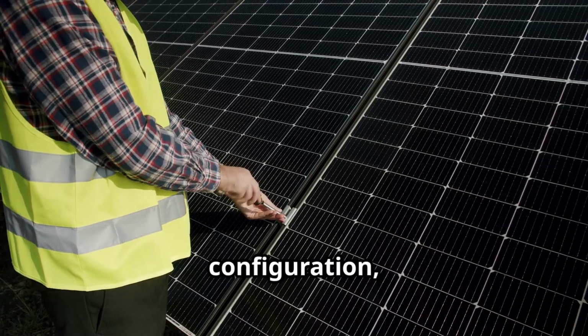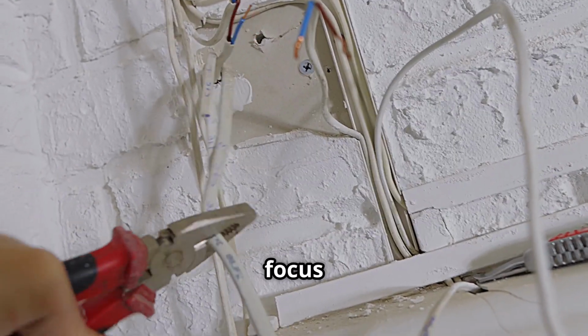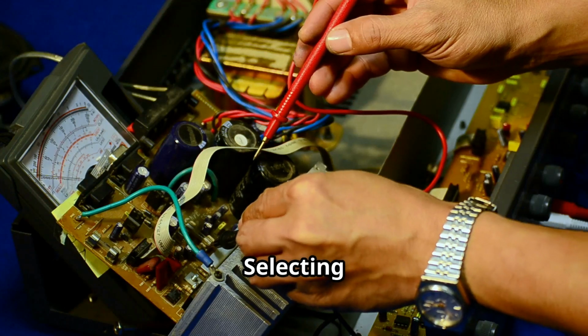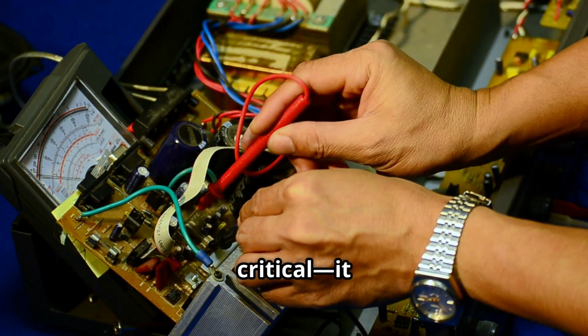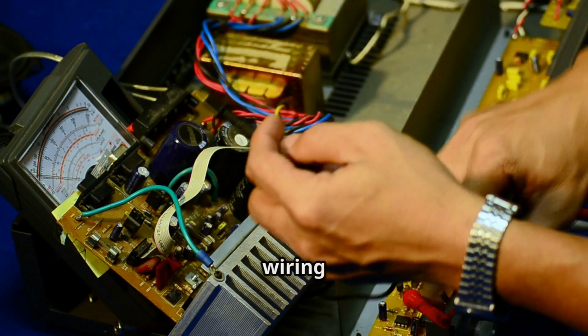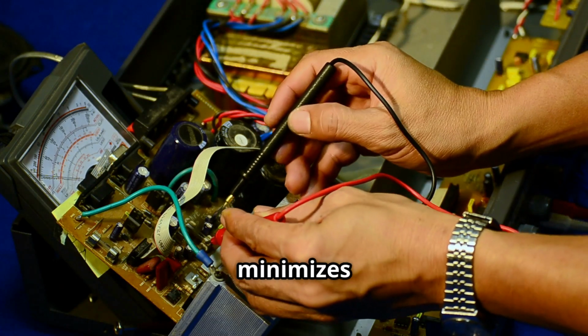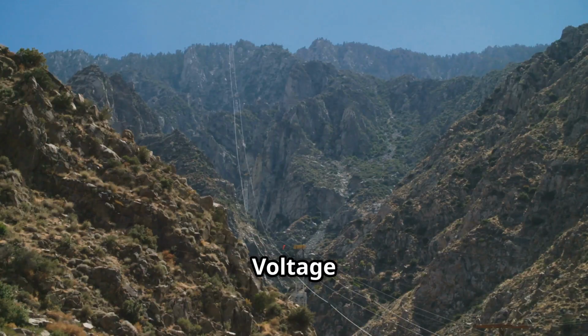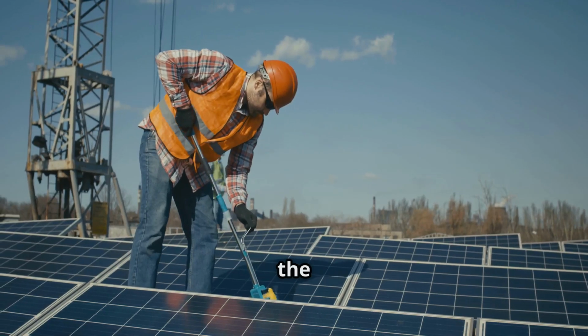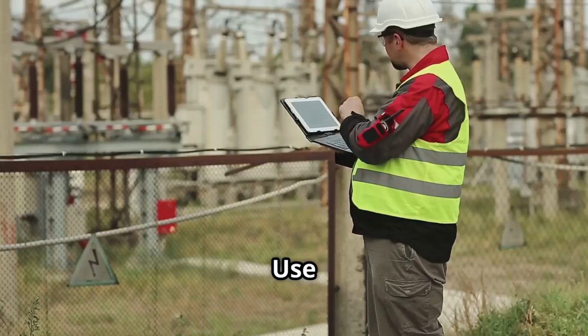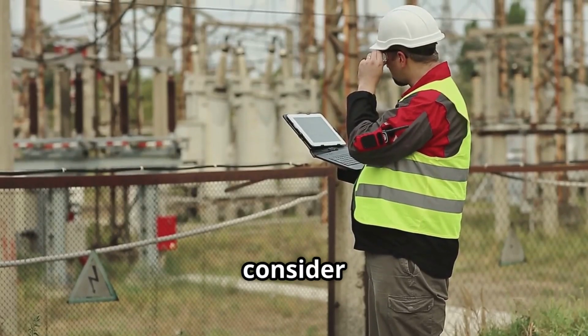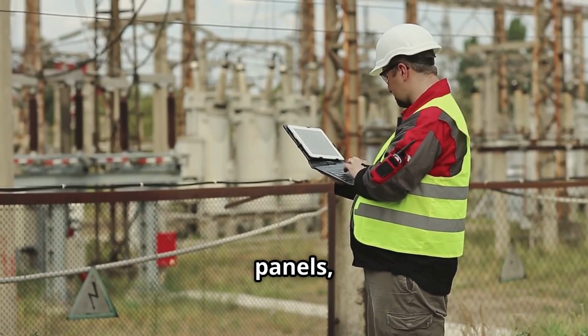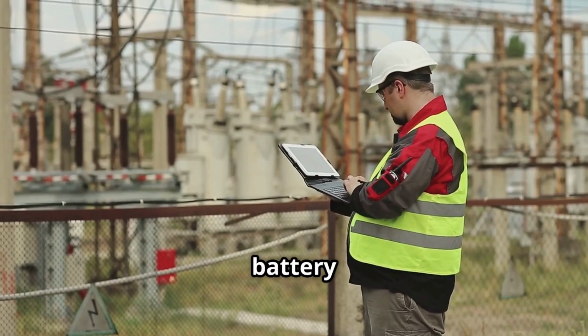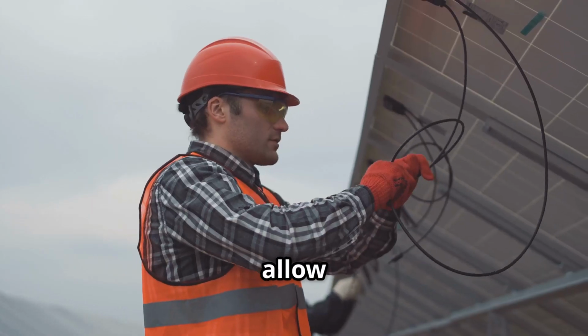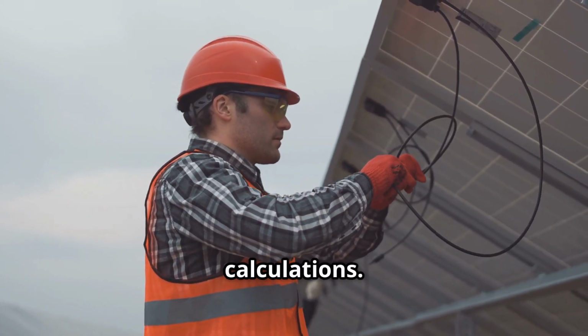Once you've decided on the configuration, the next step is to focus on wire sizing. Selecting the correct wire gauge is critical. It determines the amount of current your wiring can safely handle and minimizes voltage drop. Voltage drop is the loss of voltage over long cable runs, which can reduce the efficiency of your system. Use wire sizing calculators and consider factors like the distance between panels, the charge controller, the battery bank, and the inverter. Always allow for a margin of safety in your calculations.